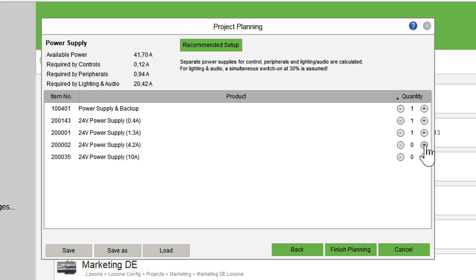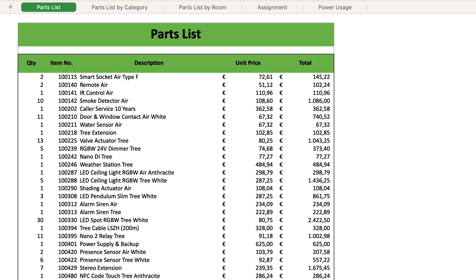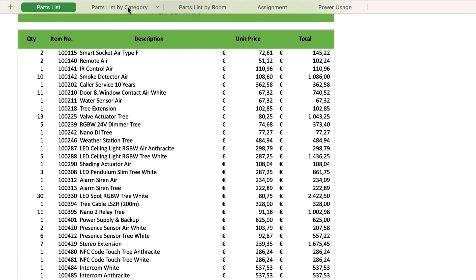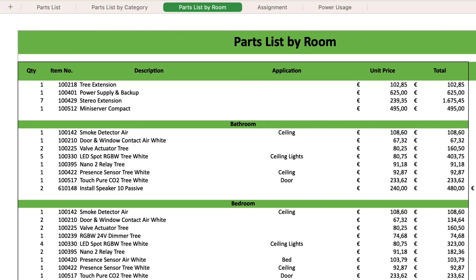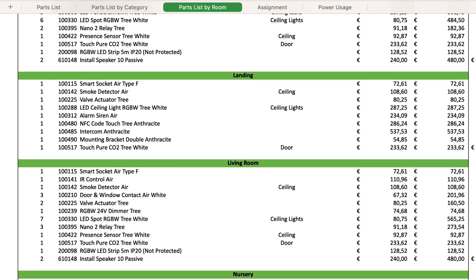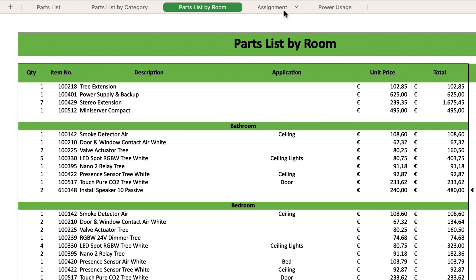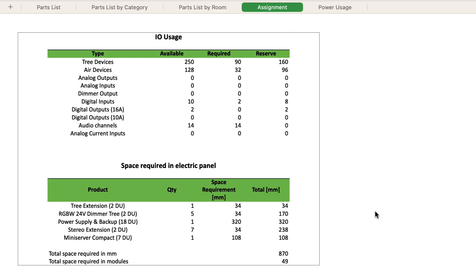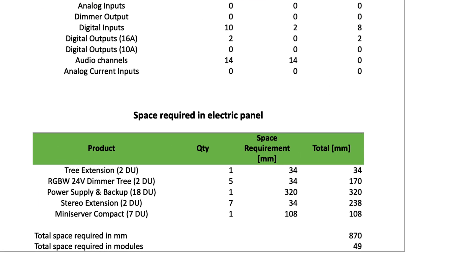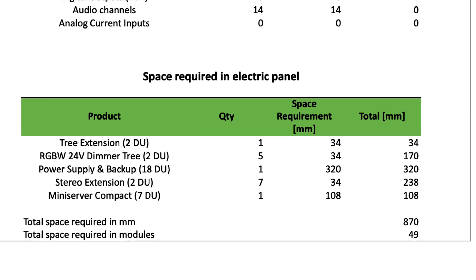The project planning tool also calculates the required power of the power supplies. At the end we get a complete list of all the components that can be used to create an offer, clearly sorted by room or category, as well as an overview of the assignment of the inputs and outputs. It is also important to know how much space is required — all components from the control cabinet are listed here with size, so we know exactly how big the control cabinet has to be.